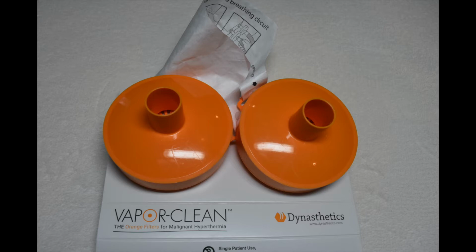1. Turn off the anesthetic vaporizer. 2. Increase fresh gas flow to greater than 10 liters per minute for at least 90 seconds to flush the vapor from the anesthesia delivery system. 3. Place one of the Vapor-Clean canisters in the inspiratory port of the anesthesia machine, and the other canister on the expiratory port of the anesthesia machine. 4. Replace the breathing bag and connect a new breathing circuit between the patient and the vapor-clean canisters. Maintain fresh gas flow at greater than 3 liters per minute.